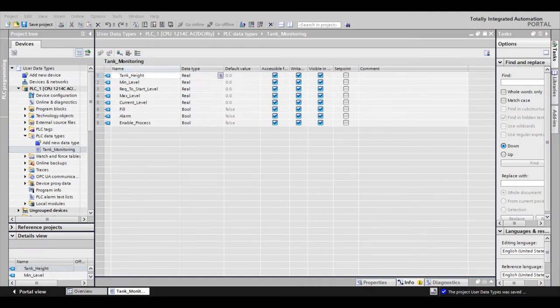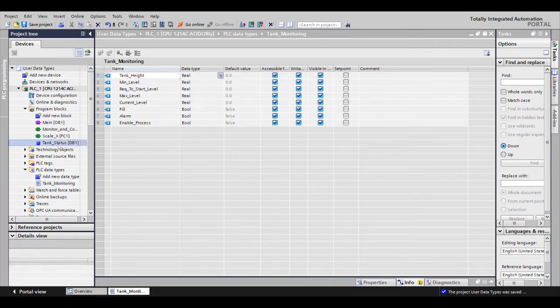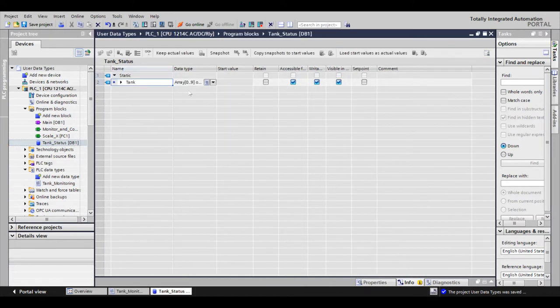Now that I've created the data structure I want, what I'm going to do is add a data block and create an array of that data structure. Because we have 10 tanks, I'm going to create an array from 0 to 9 of tanks.